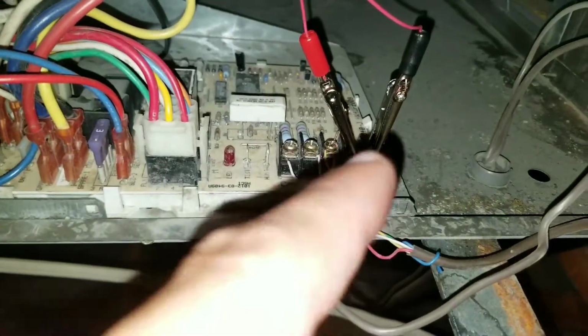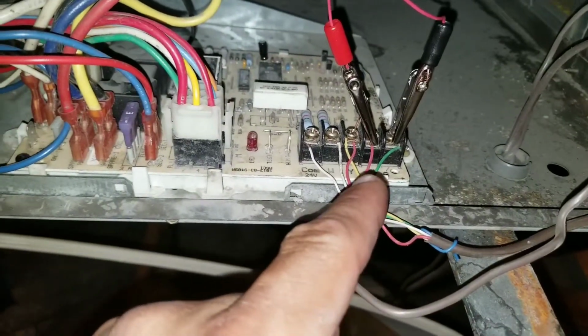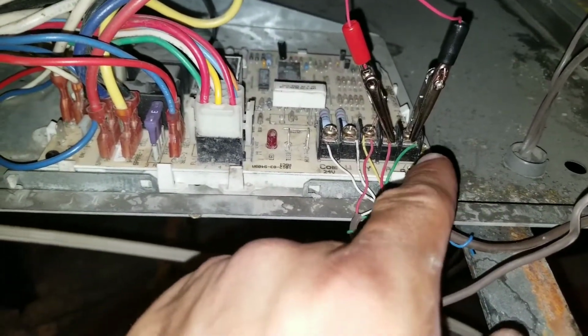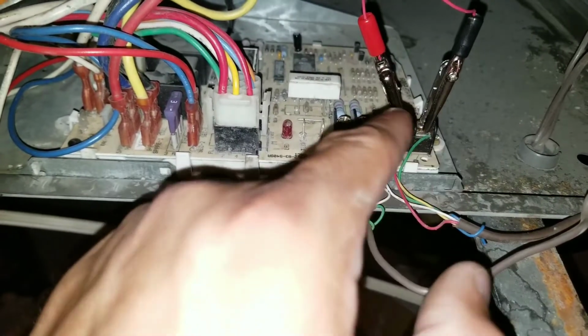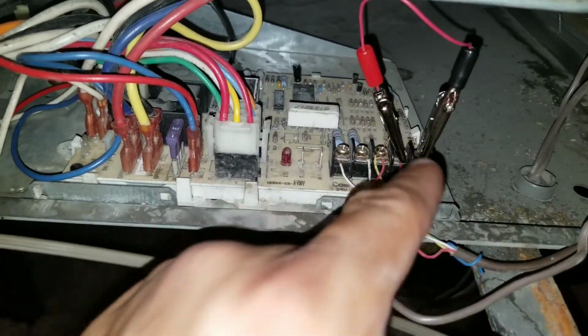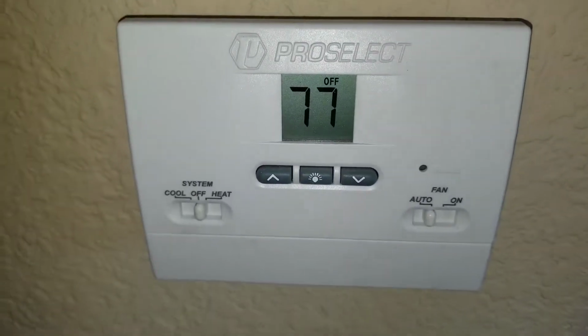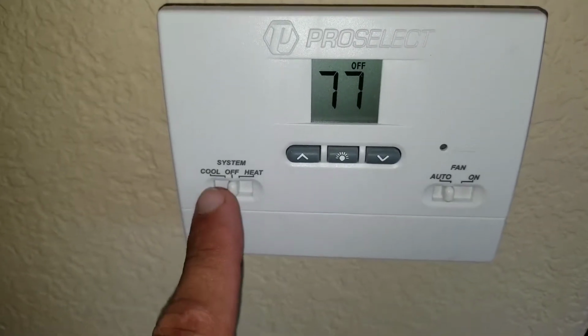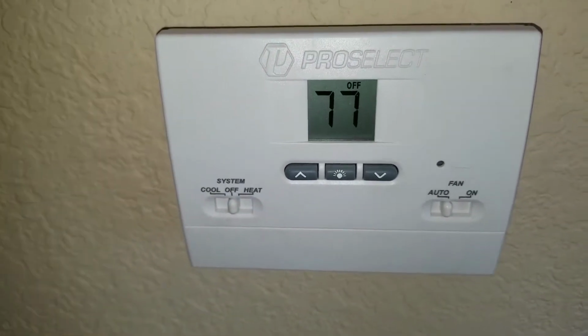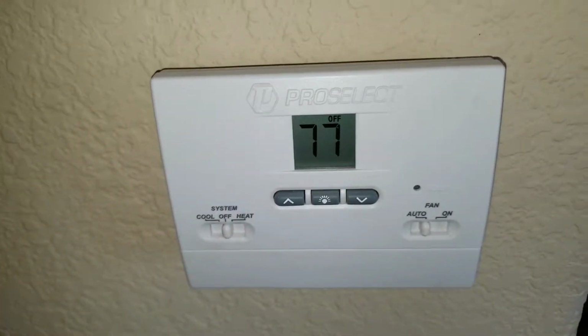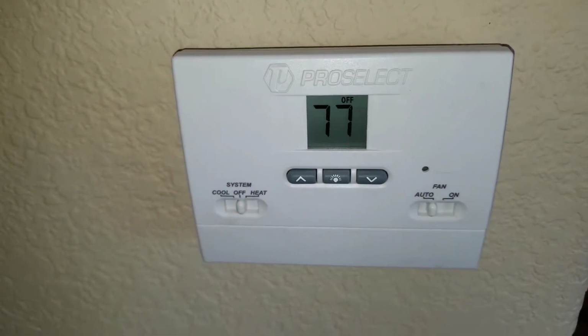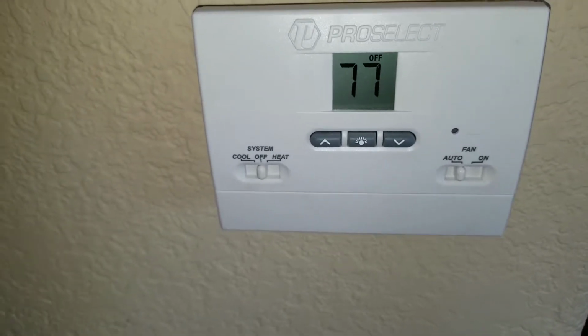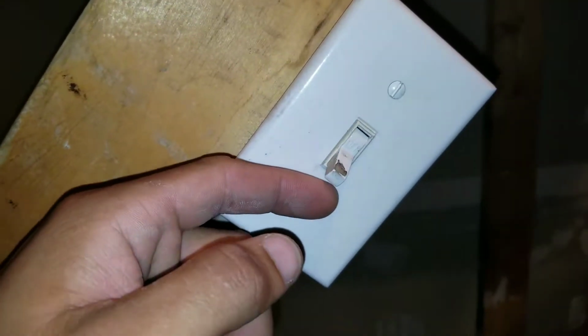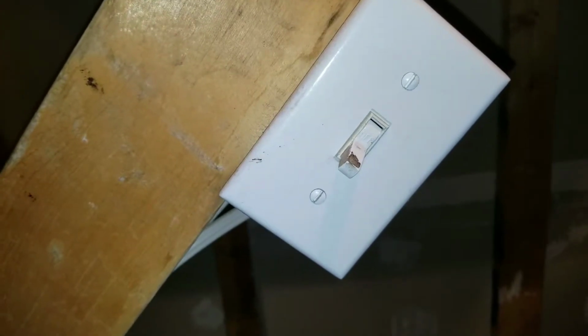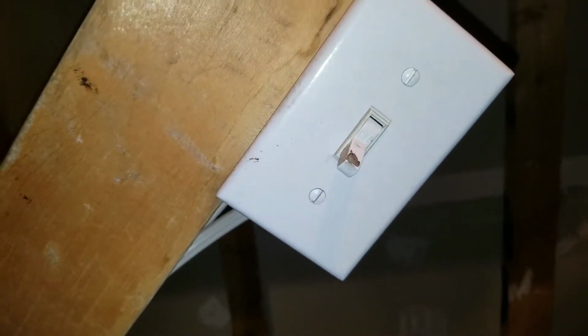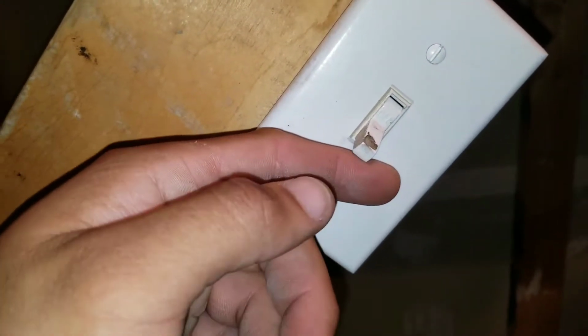Here I have my alligator clip on my R terminal, that's my 24 volts, and my G terminal, that's going to be for my blower. This is going to cause it to bypass my thermostat. Here is my thermostat, and you can see it's on the off and auto position. So right now my thermostat is not sending a signal to my furnace board calling for heat, cool, or for the fan. I'm going to turn the system on, and because I jumpered it here at the furnace board, I'm bypassing my thermostat and my blower should turn on.